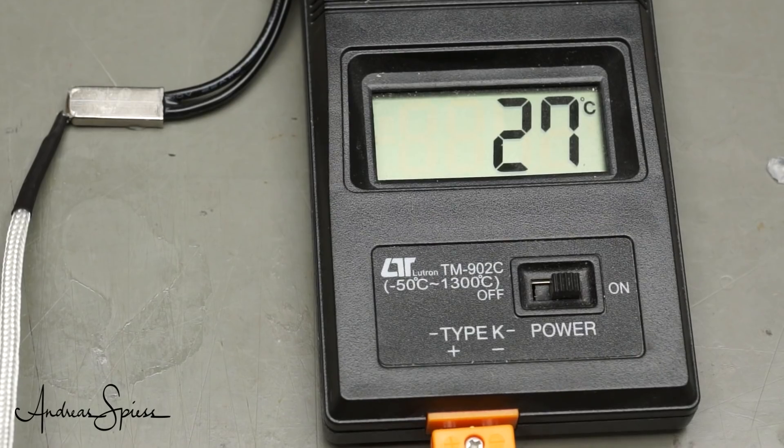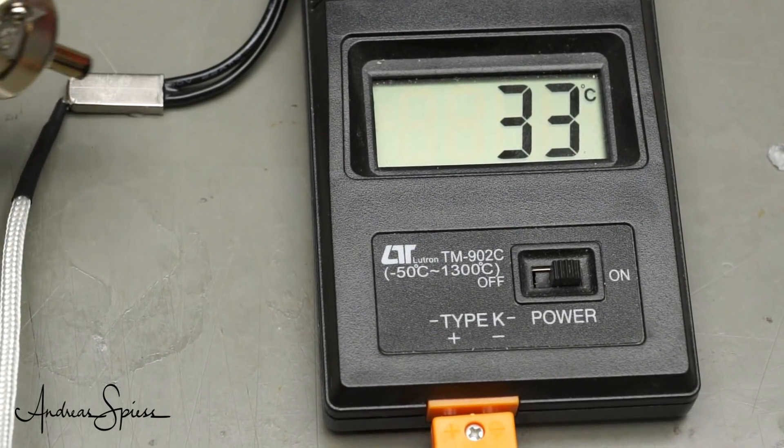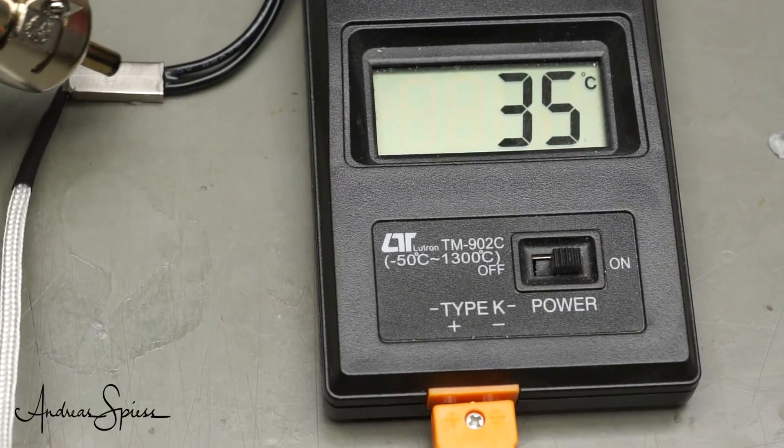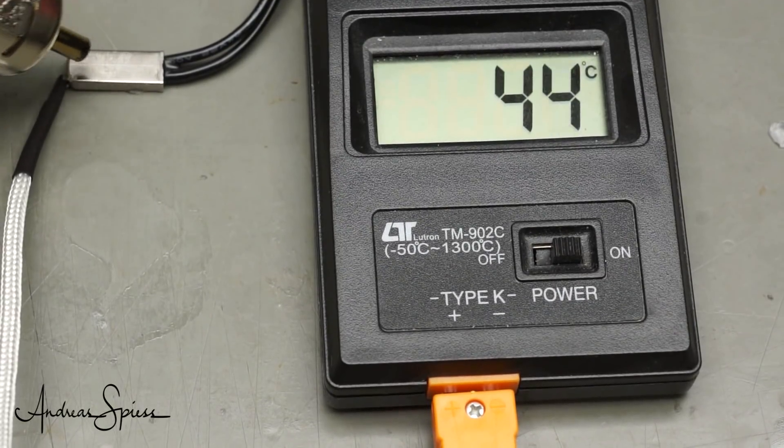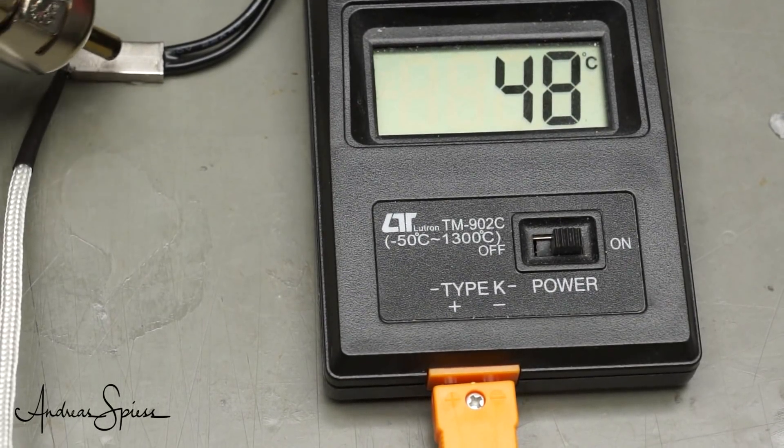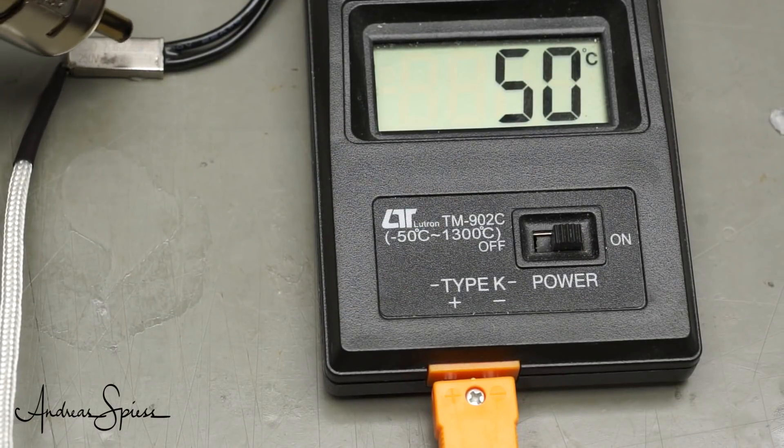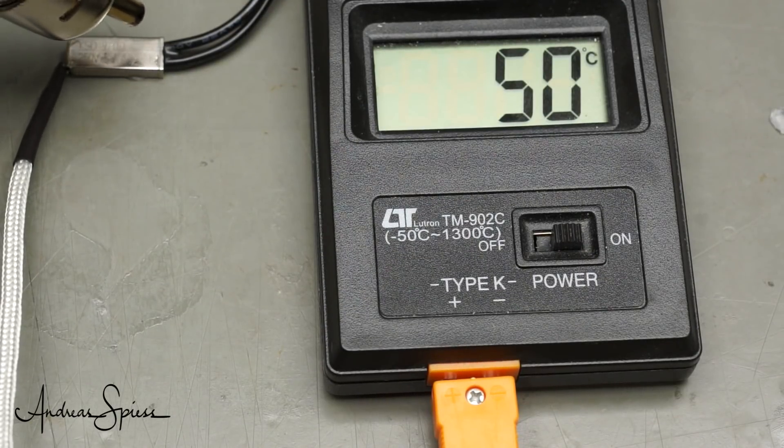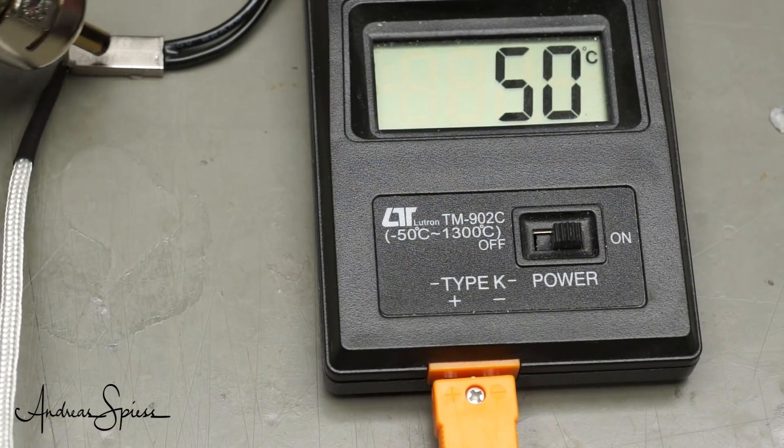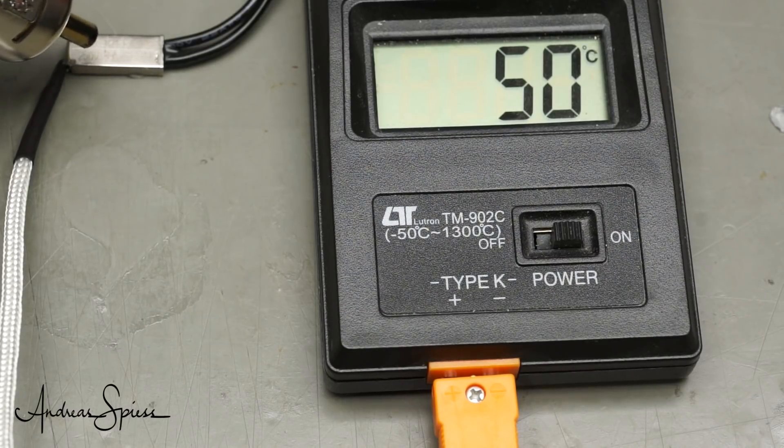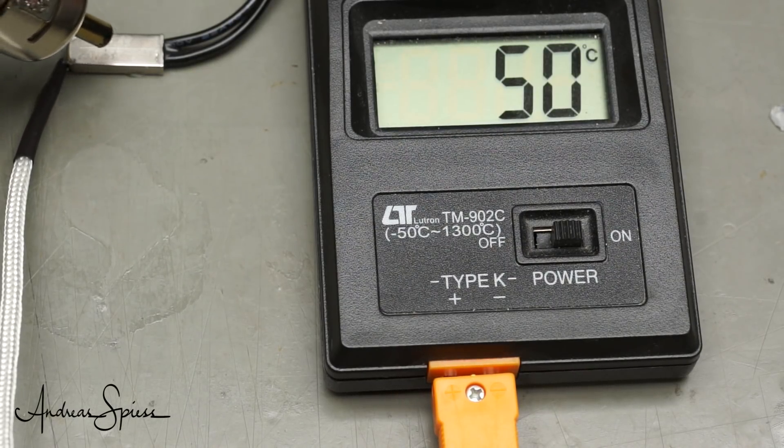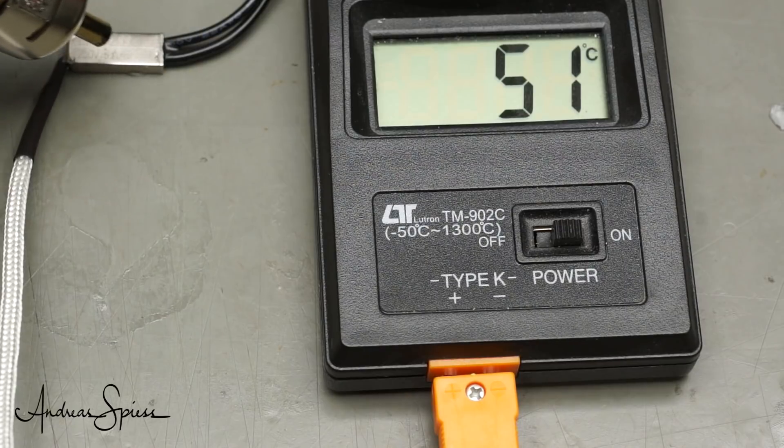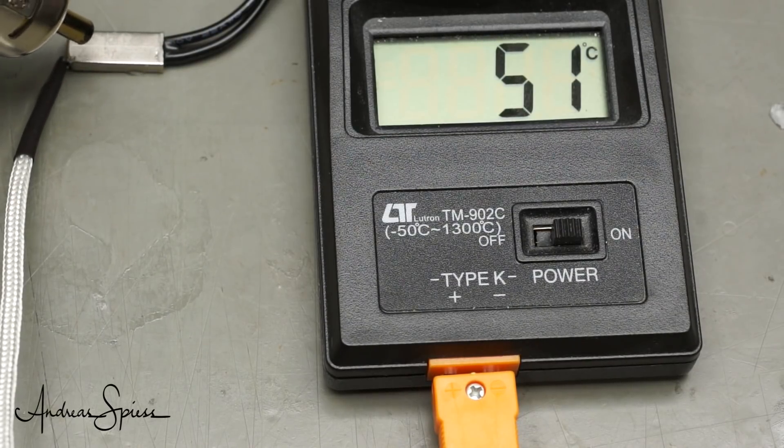We connect a multimeter to the two cables of the temperature switch and a thermocouple below it. Now I start to heat the element. At about 50 degrees, the contact closes and has a resistance of around 5 ohms, sometimes even lower. My measuring method is not very accurate, but sufficient for this purpose.